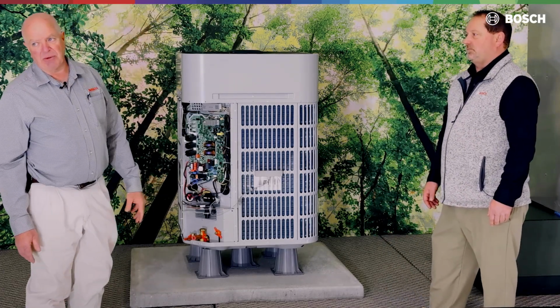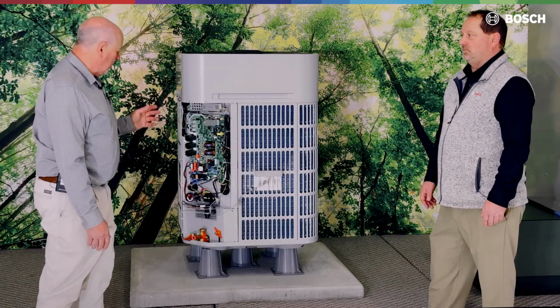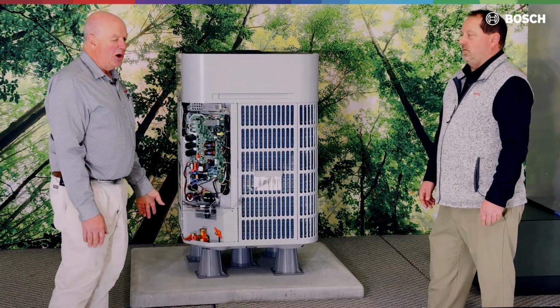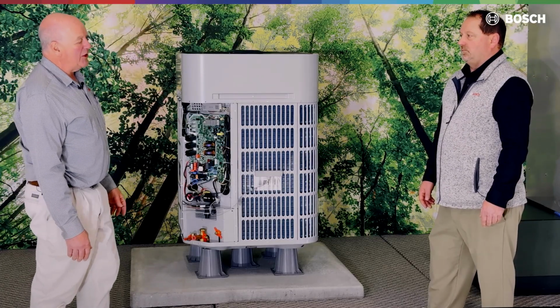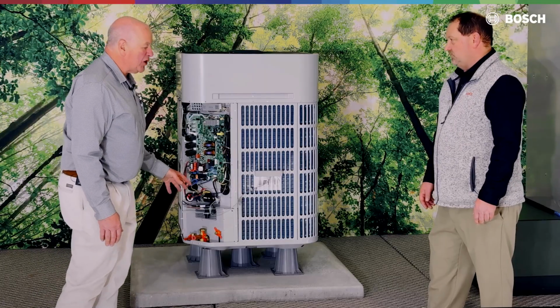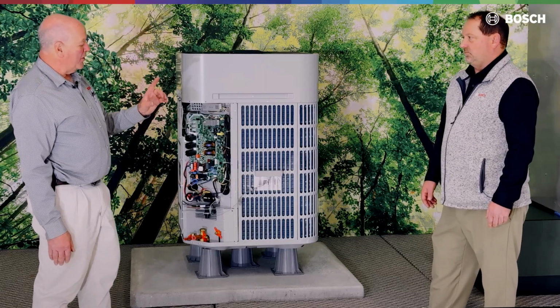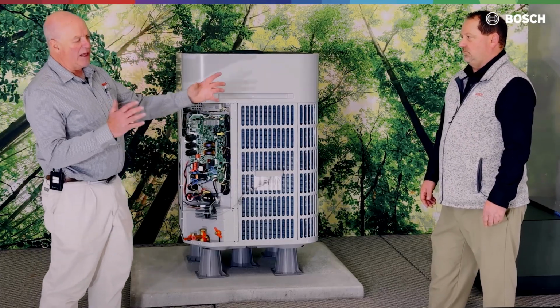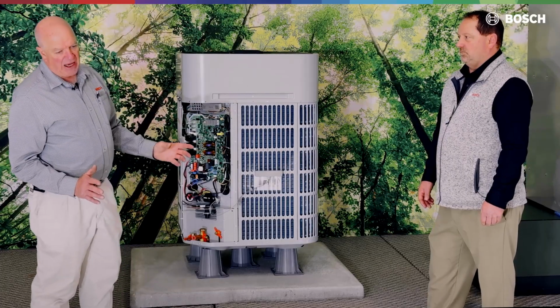We're going to do a triple vac. A triple vac system is where we pull this down to 350 micron. We're going to break that first vac with nitrogen. Our goal is to get that pressure above 0 pounds, to 1 psi. Not looking at 2,000 psi, 1 psi of nitrogen.